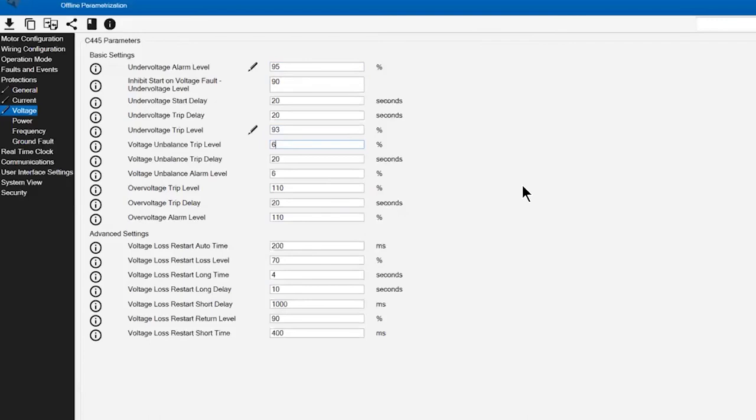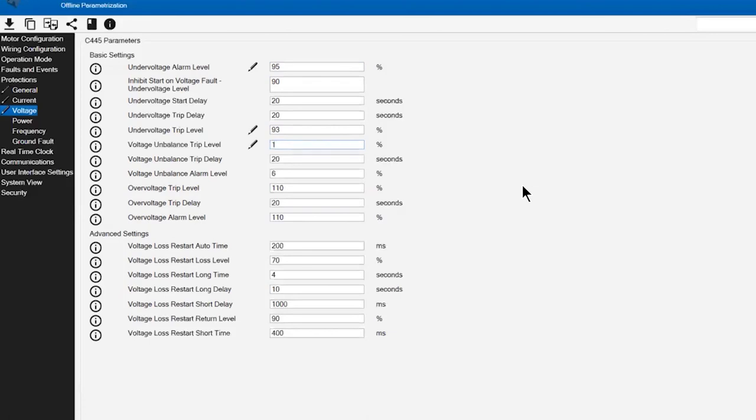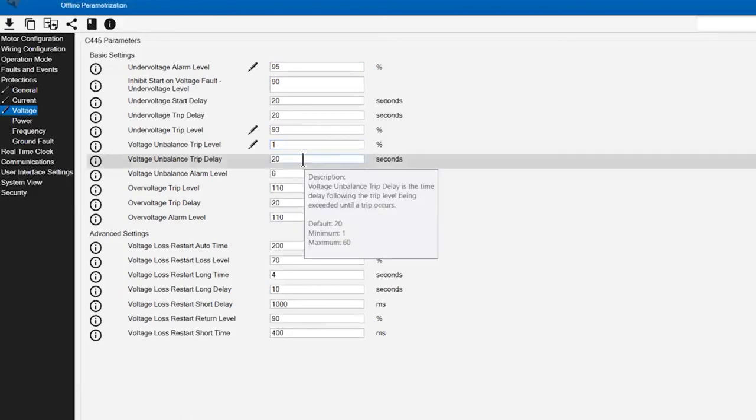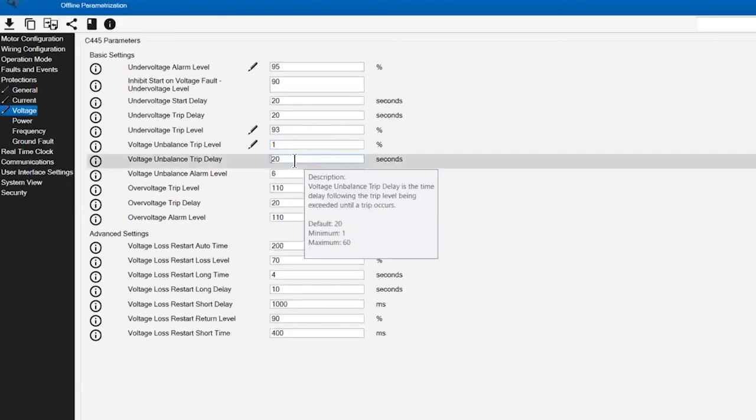Understand that a very small level of voltage imbalance is going to generate a larger value in current imbalance. So I'm going to back that percentage down to a 1% value, and that gets us in line with the current imbalance that we've already configured.